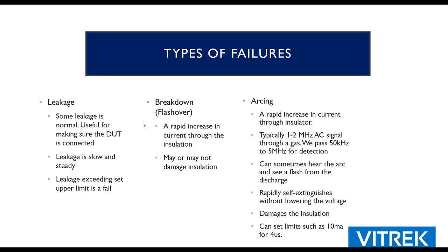We have a special circuit in the testers that is really looking for the high frequency that's present when there is a flashover, when there is an arc. You can set that limit in both amplitude and duration, and we can cue in on that, detect it, and flag a unit as a failure for that reason.